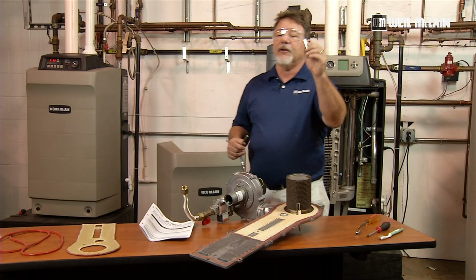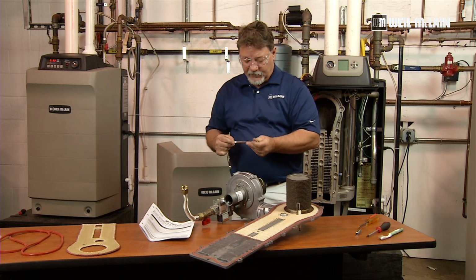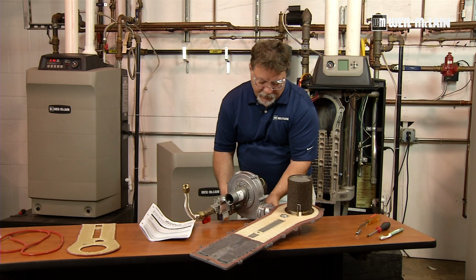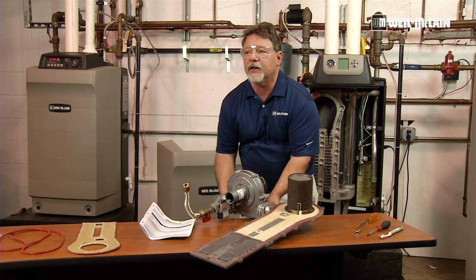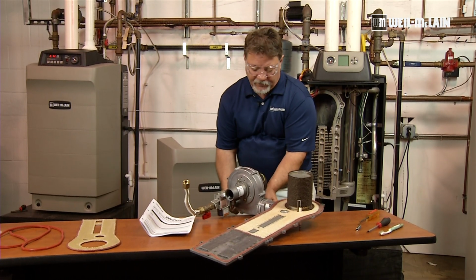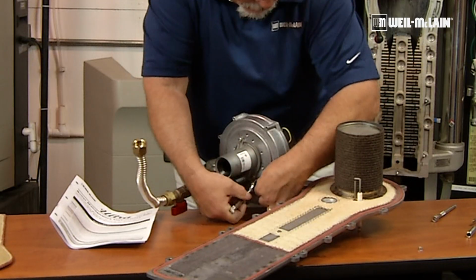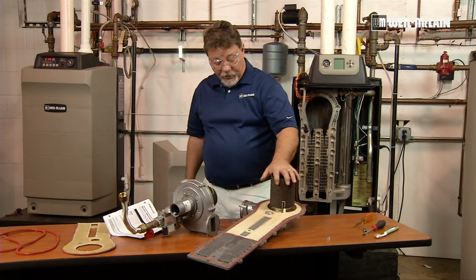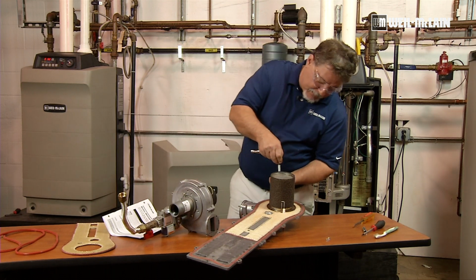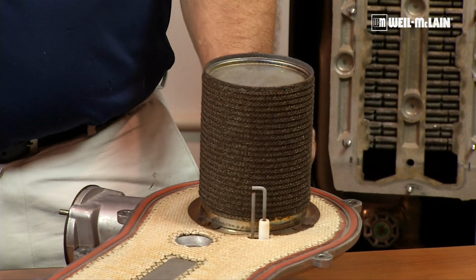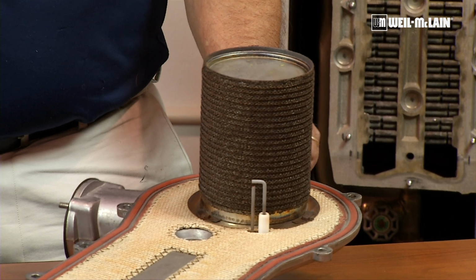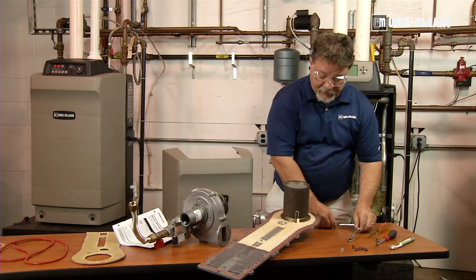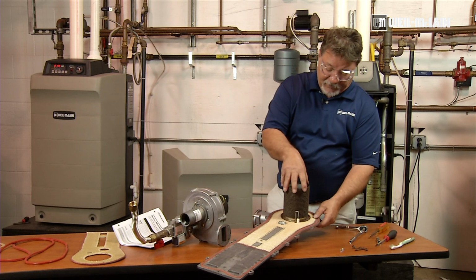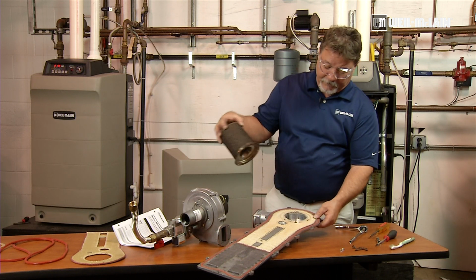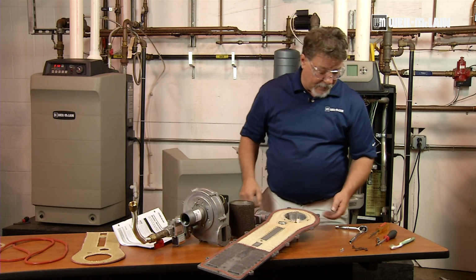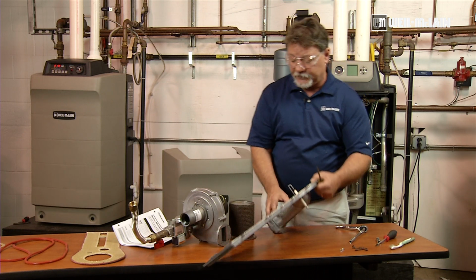We're going to start with the number 9mm socket, and I'm going to remove a nut. And I'll do the other one in just a moment, but that holds the blower assembly to the manifold. So the burner is mounted on top of the gasket material. So to change the gasket material, you have to remove the burner. So now I've removed the bolts that hold the burner to the cover plate, and I'm simply going to pull the burner off.